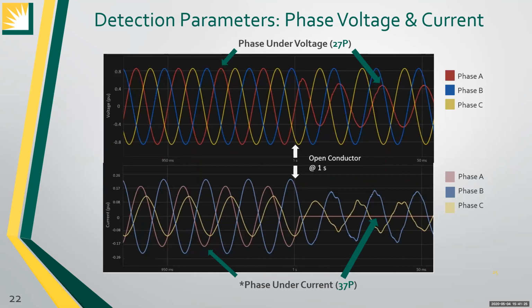Similarly to the approach we took with the sequence component parameters, we decided upon using both changes in phase voltage and phase current in our final detection logic design. Here we have both graphs for the system's phase voltage and phase current before and after the open conductor occurs at 1 second. Throughout our simulations, we observed that the amplitude of the phase voltage of the open phase consistently drops, in addition to the phase current of the open phase dropping to 0. We also observed changes in the amplitude of the two healthy phases' currents, but the behavior of this change, whether the amplitude increased or decreased, was not consistent, and therefore we did not include a parameter in which the other two phases are considered for open conductor detection. Thus, we only included the phase voltage and phase current for the open phase via phase under voltage 27P and phase under current 37P. Next slide, please.